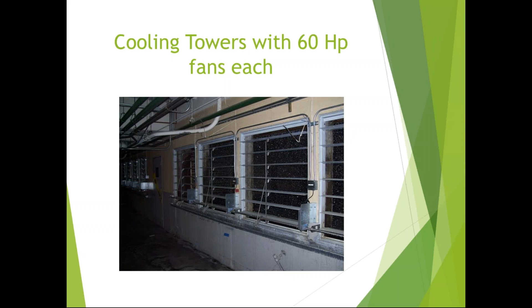We're always drawing in San Francisco air, 55 to 65 degrees. I think people understand where I'm going with this, you could use that as an economizer. It's drawn in through the cooling towers and then shot out to the atmosphere, that's the last part of the heat rejection. So that's the cooling tower fans.